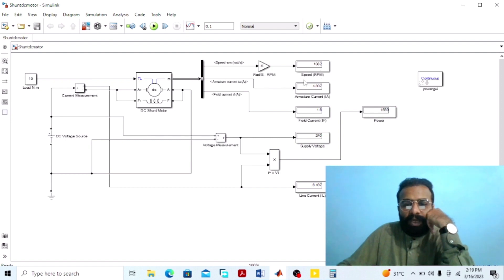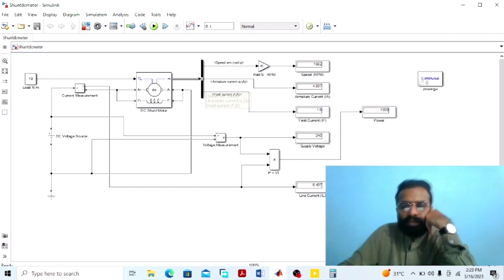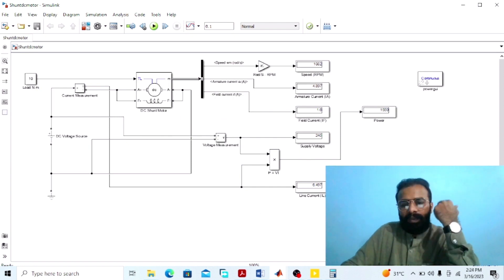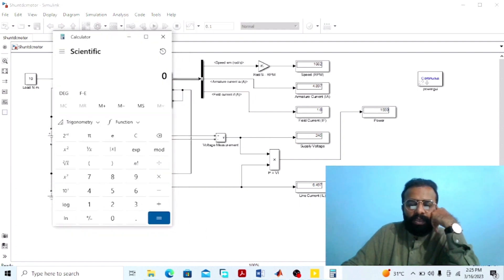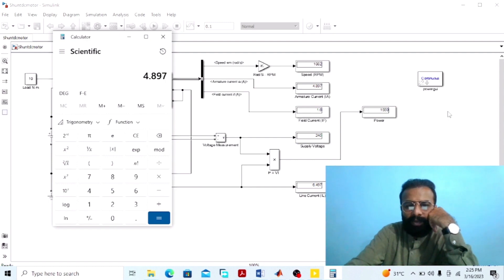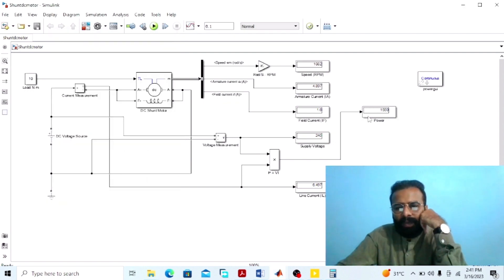Here we are getting the speed from the bus selector output as 1082 RPM. The armature current is 4.897 amperes, the field current is 1.6 amperes, and the supply voltage is 240 volts. The line current is 6.497 amperes. To verify: line current equals armature current plus field current, which is 4.897 + 1.6 = 6.497 amperes — confirming the same value. The power drawn from the main supply is 1559 watts, calculated as supply voltage (240 V) multiplied by line current (6.497 A).